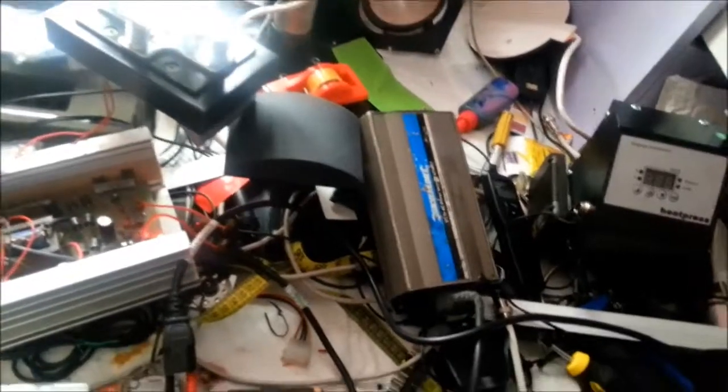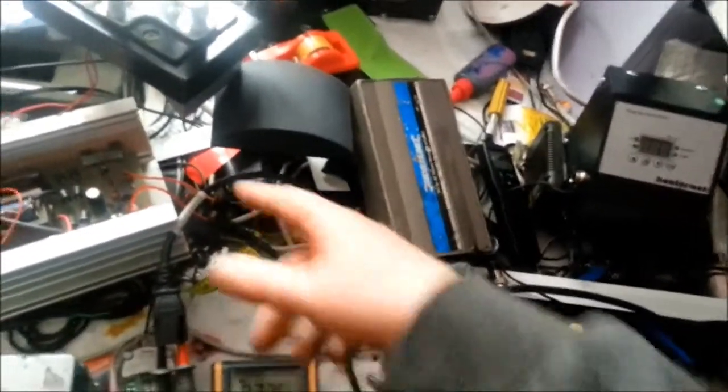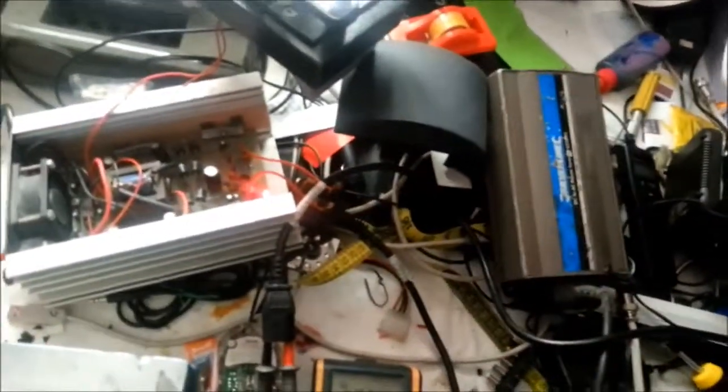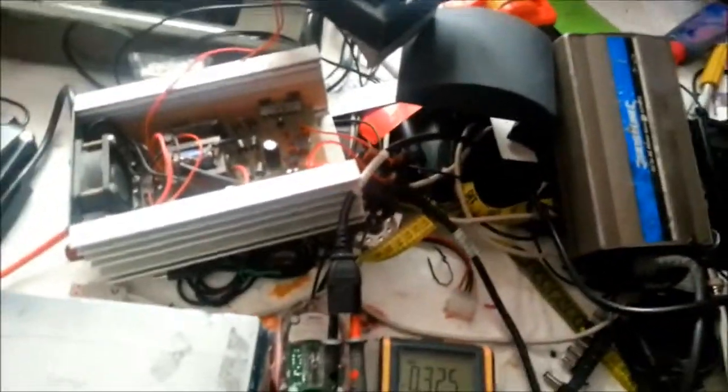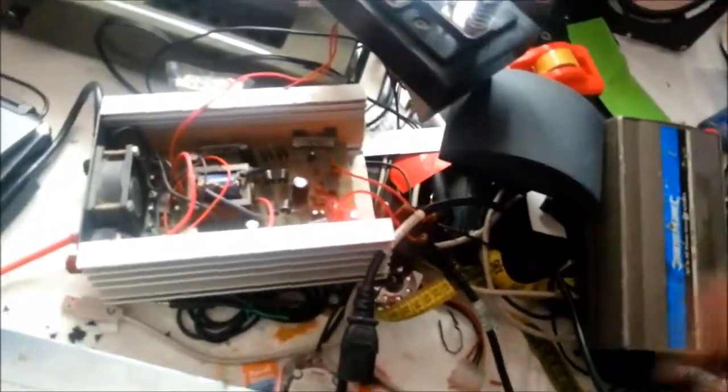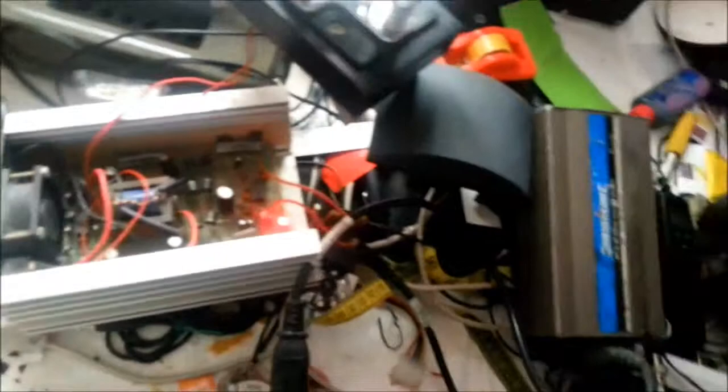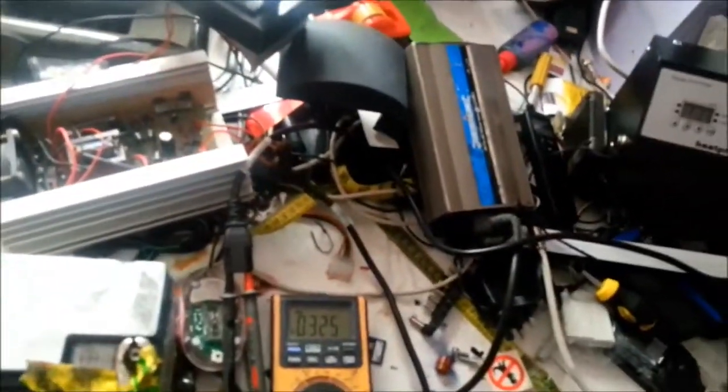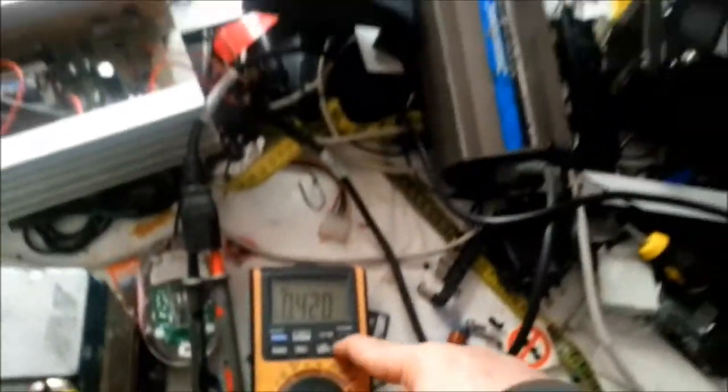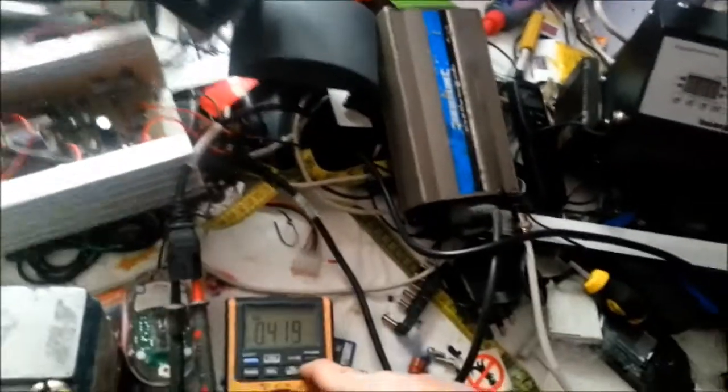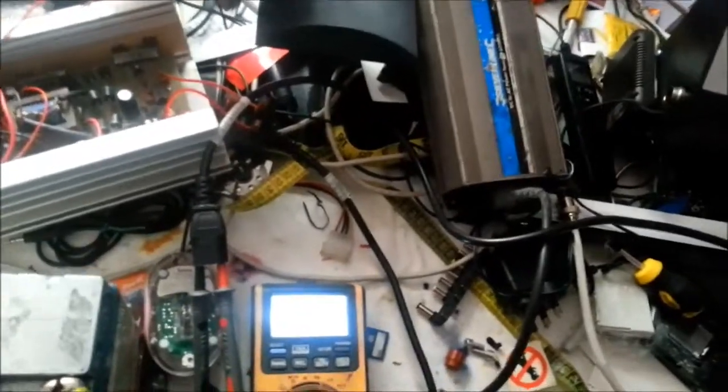So I had to check if we've got the right output voltage on this and it hasn't dropped to 180 or something daft over the years. I noticed according to this I've got 0.4 volts AC. I thought that's strange because 0.4 volts AC wouldn't run this.